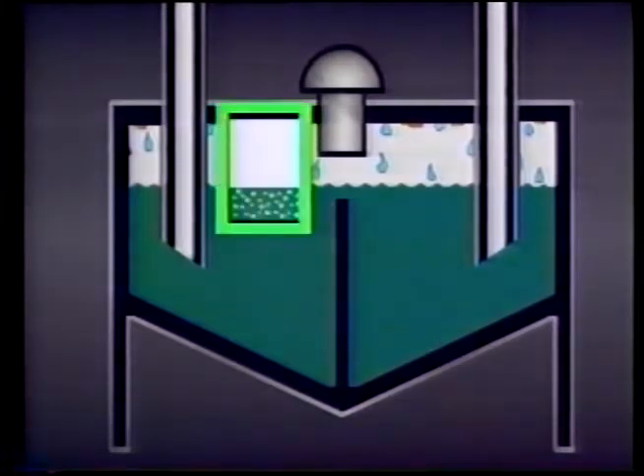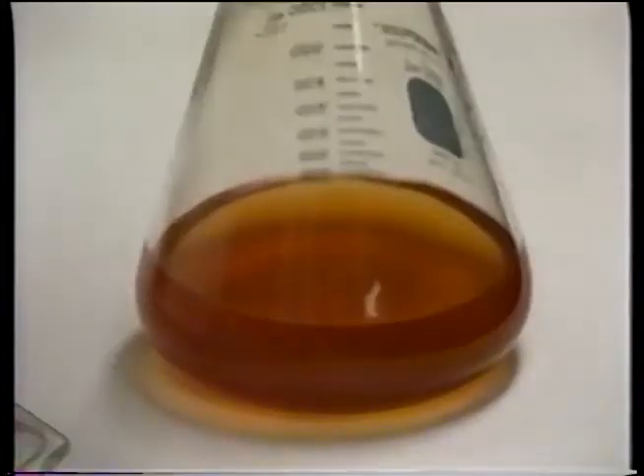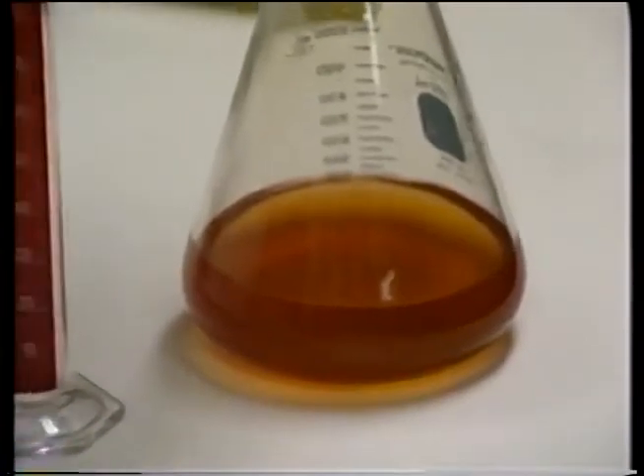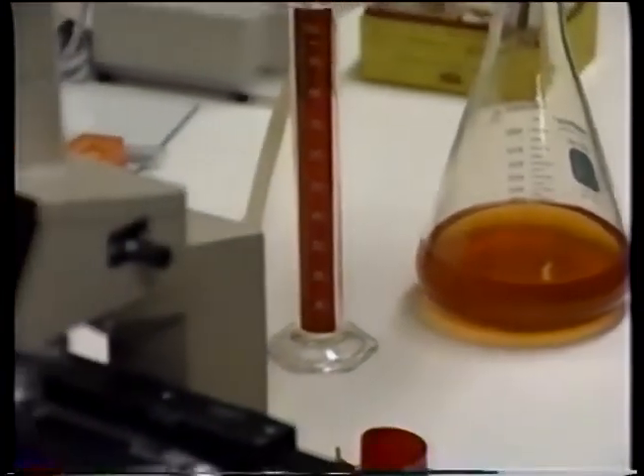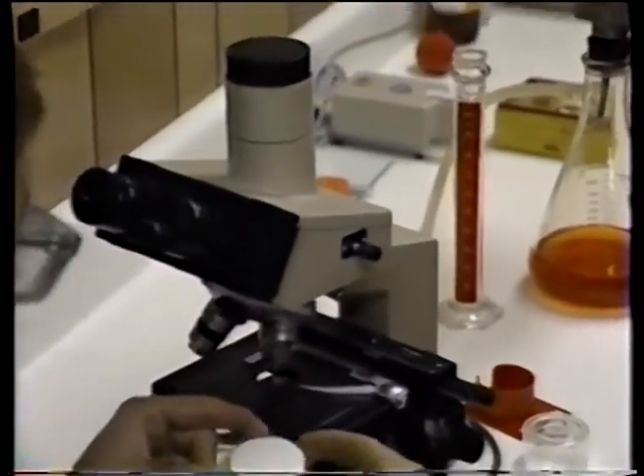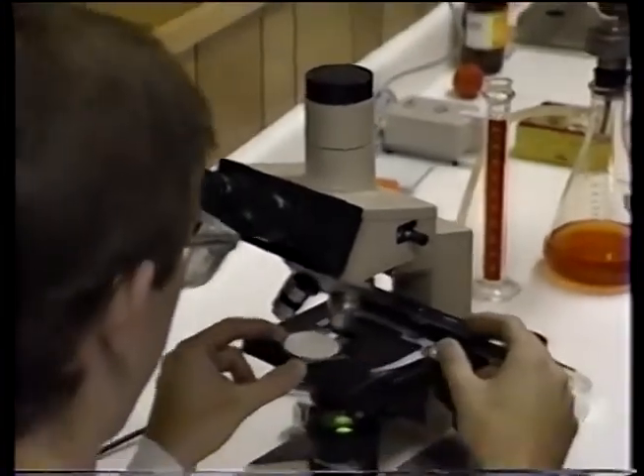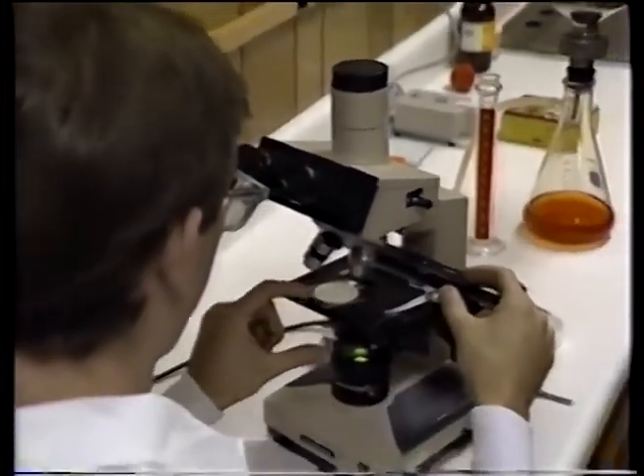Evaporation also reduces the fire resistance of the fluid since less water is available. The loss of water also affects the viscosity of a water-based fluid. When using water-based fluids, it's a good idea to have the viscosity checked by a lab periodically to make sure the system is being properly protected.